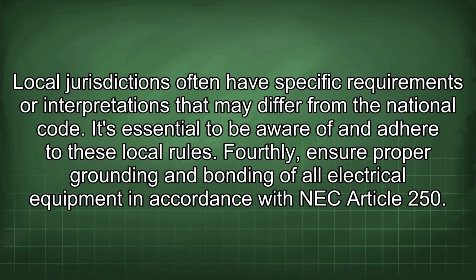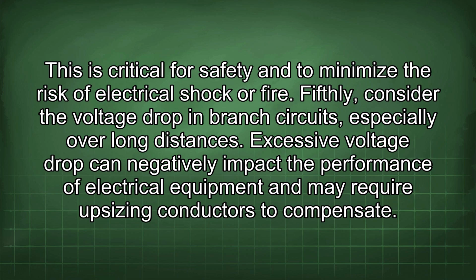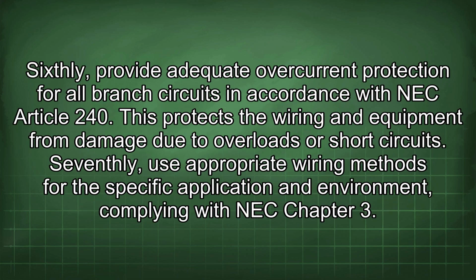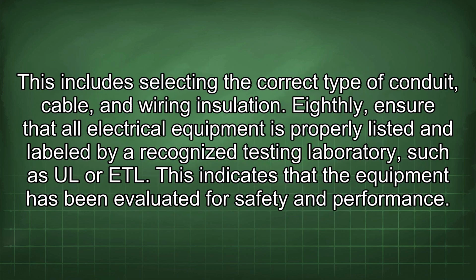Fourthly, ensure proper grounding and bonding of all electrical equipment in accordance with NEC Article 250. This is critical for safety and to minimize the risk of electrical shock or fire. Fifthly, consider the voltage drop in branch circuits, especially over long distances. Excessive voltage drop can negatively impact the performance of electrical equipment and may require upsizing conductors to compensate. Sixthly, provide adequate overcurrent protection for all branch circuits in accordance with NEC Article 240. This protects the wiring and equipment from damage due to overloads or short circuits. Seventhly, use appropriate wiring methods for the specific application and environment complying with NEC Chapter 3. This includes selecting the correct type of conduit, cable, and wiring insulation. Eighthly, ensure that all electrical equipment is properly listed and labeled by a recognized testing laboratory such as UL or ETL. This indicates that the equipment has been evaluated for safety and performance.